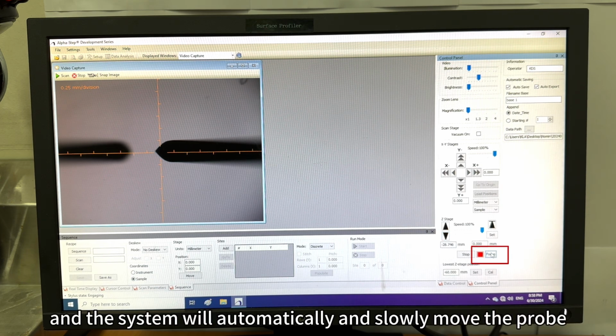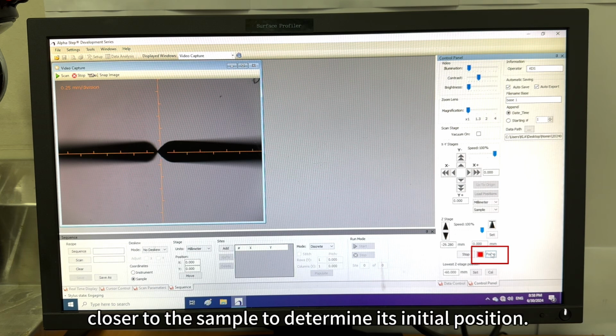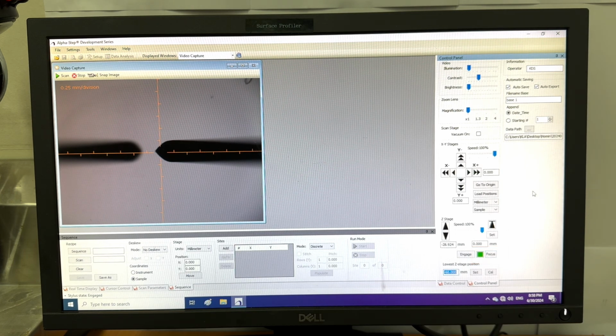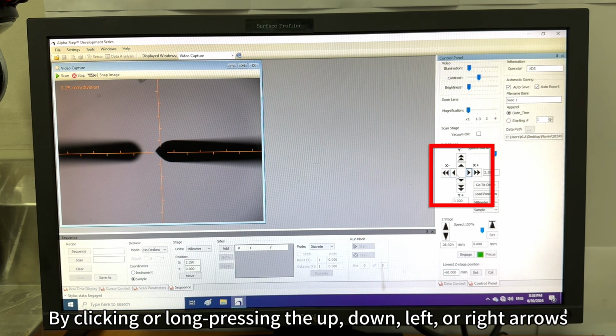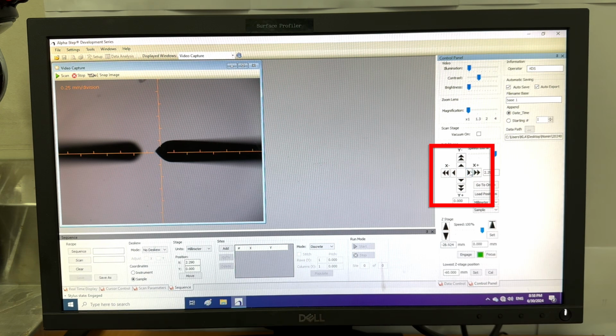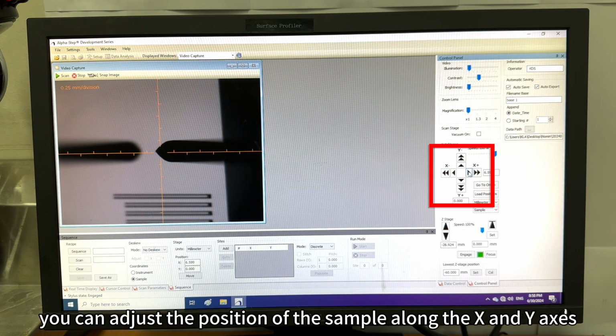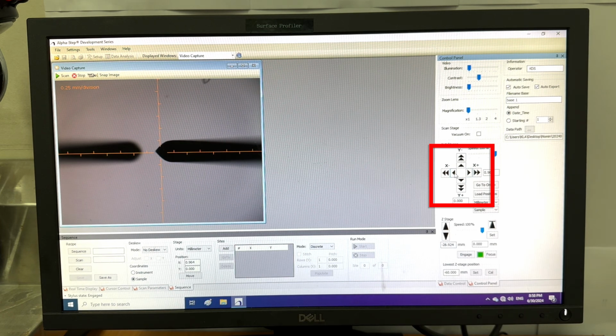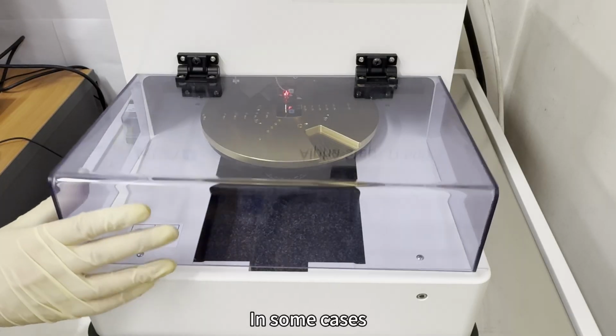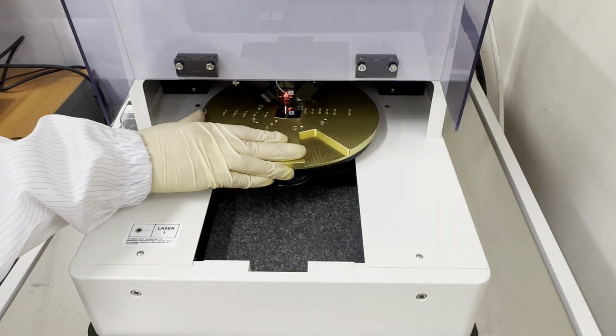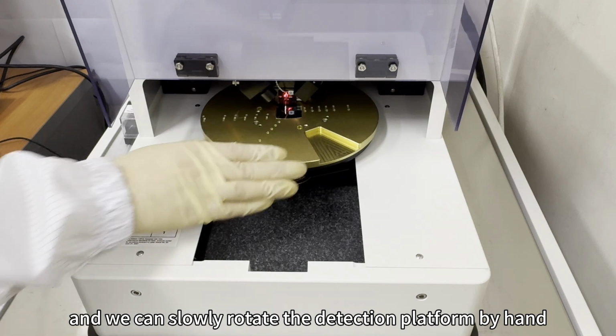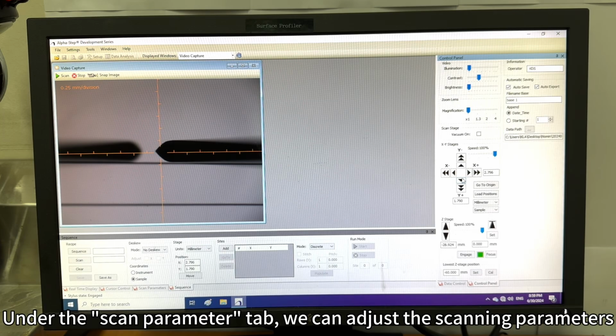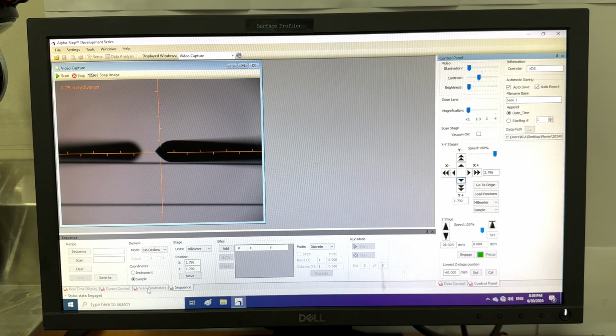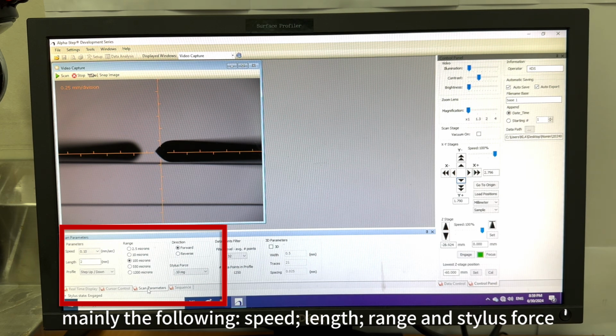Click the focus button, and the system will automatically and slowly move the probe closer to the sample to determine its initial position. By clicking or long pressing the up, down, left, or right arrows, you can adjust the position of the sample along the x and y axis. In some cases, angle adjustment is required, and we can slowly rotate the detection platform by hand. Under the Scan Parameter tab, we can adjust the scanning parameters, mainly the following: speed, length, range, and stylus force.